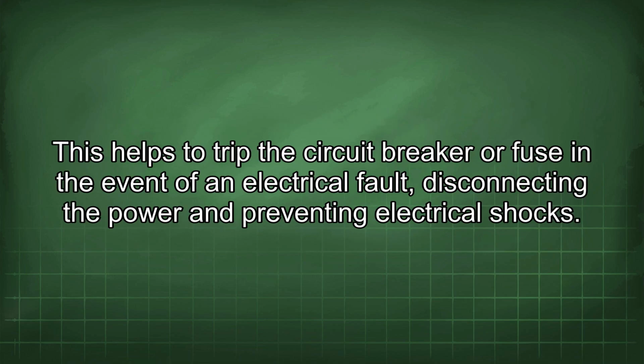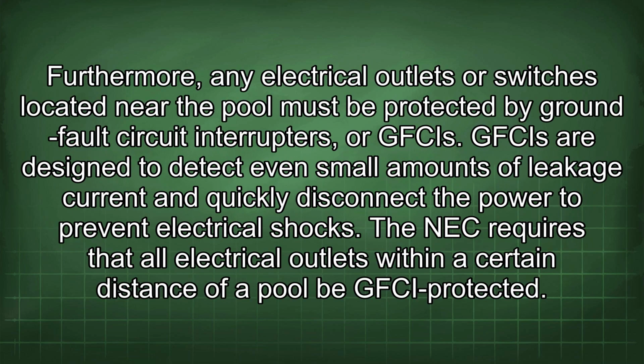This helps to trip the circuit breaker or fuse in the event of an electrical fault, disconnecting the power and preventing electrical shocks. Furthermore, any electrical outlets or switches located near the pool must be protected by ground fault circuit interrupters, or GFCIs. GFCIs are designed to detect even small amounts of leakage current and quickly disconnect the power to prevent electrical shocks. The NEC requires that all electrical outlets within a certain distance of a pool be GFCI protected.